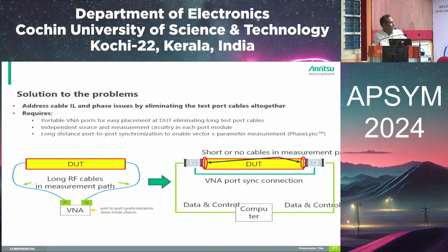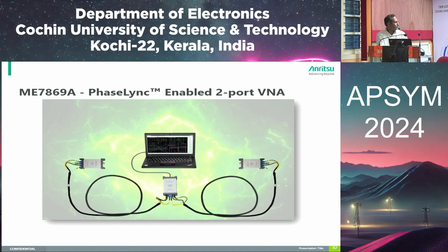The network analyzer port is extended up to the end of the DUT directly. So now you are eliminating the cable. We are connecting the ports of the cable and network analyzer directly to the measurement DUT. Whatever the length of the cable, 150 meters or 100 meters, it will be the electrical PhaseLync cable supplied by Anritsu. So these are the cables. This is a 5 meter one, and we have a solution up to 300 meters.